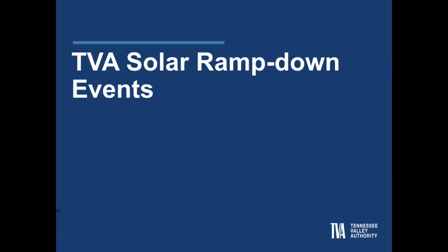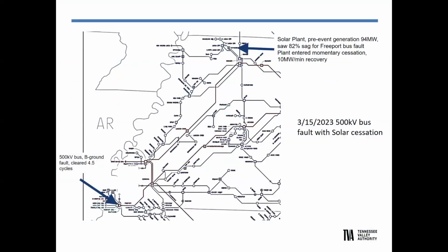Thank you. So I'm a very operational kind of guy. I like to show some experiences through situations on the system. If you go to the next slide, this is just a map of our western part of the system. Again, most of the solar is in the west for us. We had a 500 kV fault, single phase, cleared pretty quickly, 4.5 cycles, about the normal clearing time for TVA. The fault was in southwest Tennessee, and the solar plant in northwest Tennessee, roughly 400 or 500 miles away, electrically pretty distant as well.